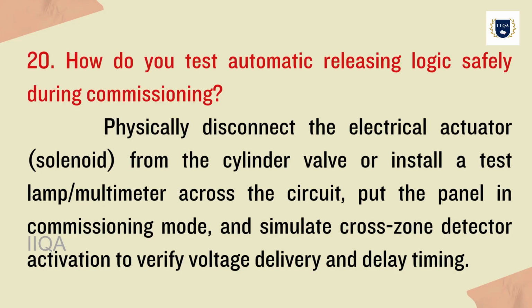20. How do you test automatic releasing logic safely during commissioning? Physically disconnect the electrical actuator, the solenoid, from the cylinder valve, or install a test lamp or multimeter across the circuit, put the panel in commissioning mode, and simulate cross-zone detector activation to verify voltage delivery and delay timing.